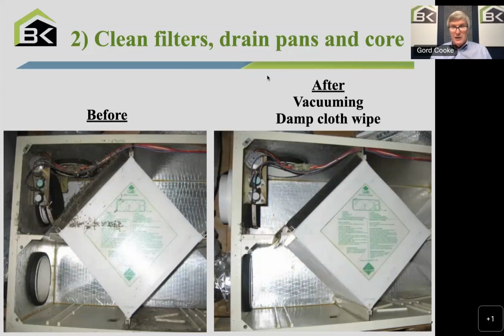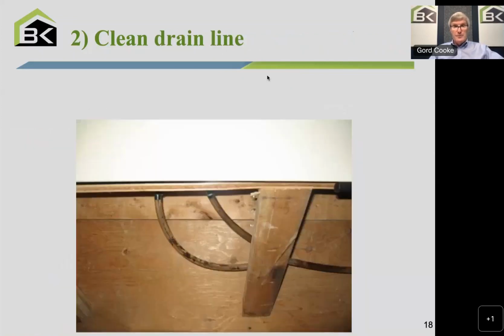And there you see on the bottom right, you're seeing the unit cleaned up. The filters have been vacuumed, the core has been washed out, damp wiped the entire unit, just getting bugs off. And that's kind of what we would like. It's not going to look perfect because it's obviously been there for years. This unit, when this picture was taken, was 15 years old. So even after 15 years, it looks pretty darn good. So just vacuuming and damp wipe is what we're looking for.